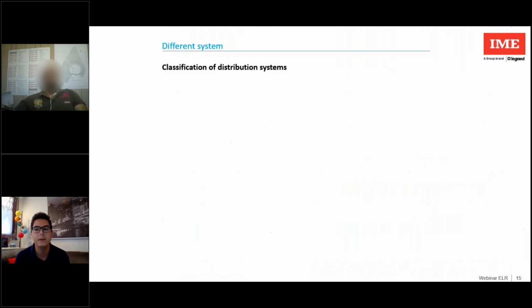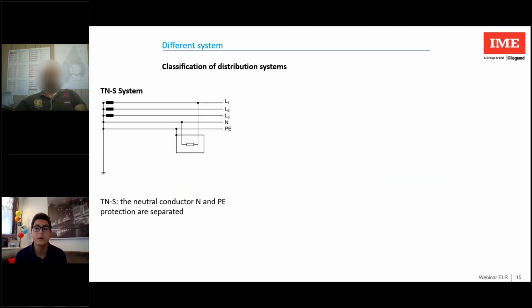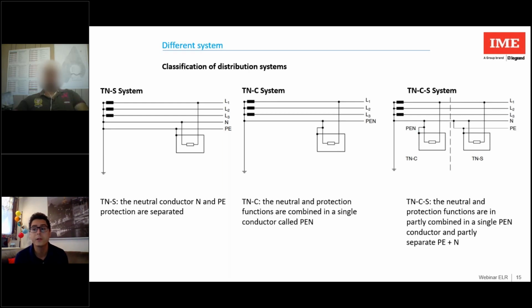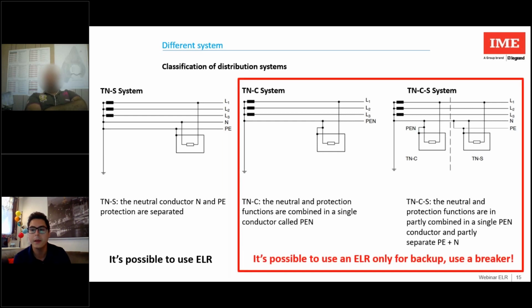Going forward, we find the TNS system, in which the neutral conductor and PE are separated. For the TNC, the neutral and protection functions are combined in a single conductor called the PEN, while in TNCS, the neutral and the protection functions are partially combined in a single PEN conductor and partially separated, PE plus N. It is therefore possible to understand that in the first one it will be possible to use an ELR, while in the other two the ELR can be used as a backup, because a breaker can be enough.